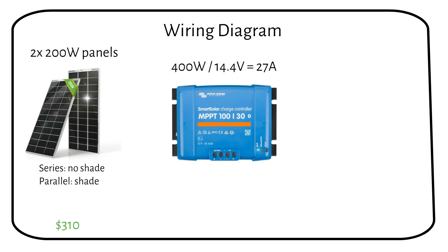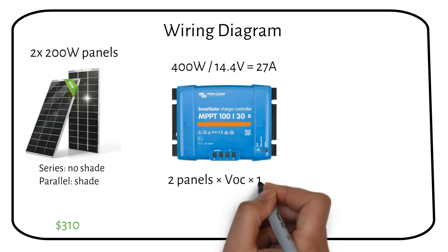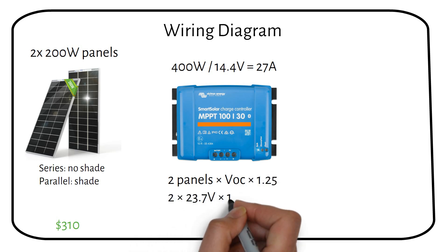Next, let's calculate the maximum input voltage. Since the panels are wired in series, the voltage adds up. The formula is 2 panels times the VOC of the panel times a safety factor of 1.25 and we get 60 volts.